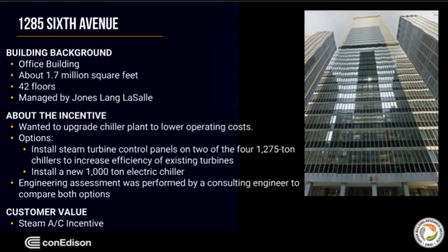One option was to install steam turbine control panels on 2 of the 4 1,275-ton chillers to increase their efficiency. The second option was to go through an elaborate and expensive process of installing a new 1,000-ton electric chiller. The engineering assessment was performed by a consulting engineer to compare both options. The initial economic analysis favored adding an electric chiller. However, after the steam AC incentive was taken into account, the customer decided to retain steam cooling capability.